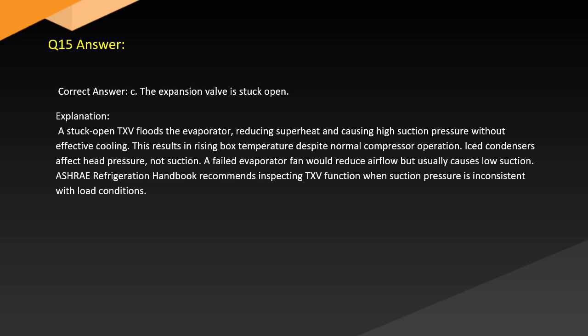Answer. Correct answer: C. The expansion valve is stuck open. Explanation. A stuck open TXV floods the evaporator, reducing superheat and causing high suction pressure without effective cooling. This results in rising box temperature despite normal compressor operation.